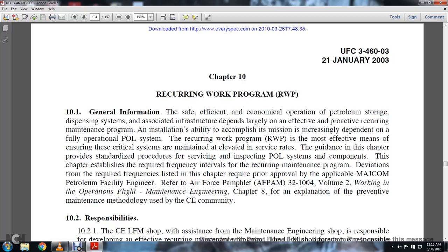10.1 General. Information on the safe, efficient, economical operation of the petroleum storage and dispensing system and associated infrastructure depends largely on an effective, proactive, recurring maintenance program. The installation's ability to accomplish its mission is increasingly dependent on a fully operational POL system. The recurring work program (RWP) is the most effective means of ensuring critical systems are maintained at elevated in-service rates. The guidance in this chapter provides standard procedures for inspecting the POL system components. This chapter establishes the required frequency intervals for the required maintenance program.